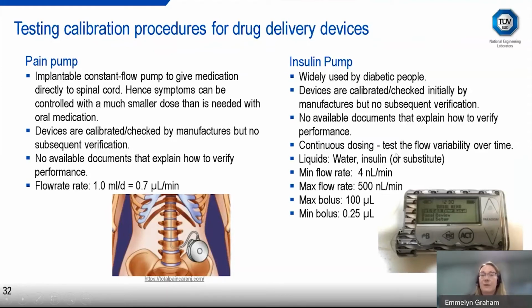The next device we're going to be testing is an insulin pump. It's widely used by diabetic people. Again, they are calibrated and checked by the manufacturers, but there may not be any subsequent verification, and there's no documents available on how you can do the performance checks. With most of these devices, you expect the dosing to be continuous. So what we want to do is have techniques that we can check that we are getting a continuous dose and we're not getting any spikes in the dose.